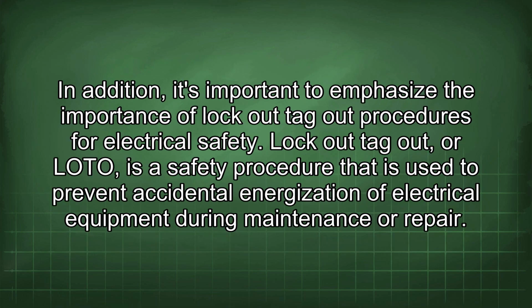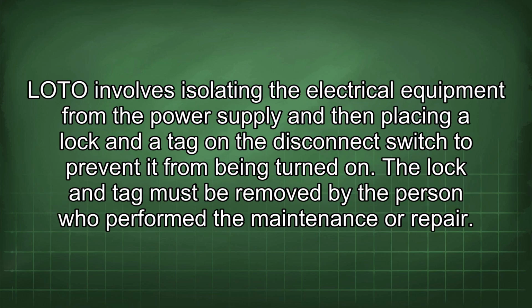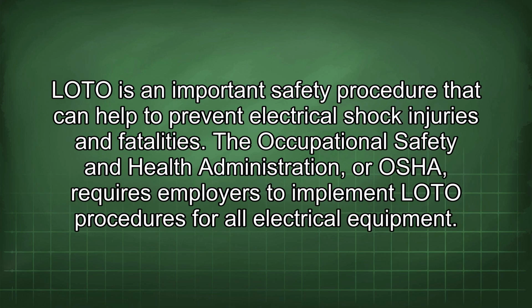hazards. In addition, it's important to emphasize the importance of lockout-tagout procedures for electrical safety. Lockout-tagout, or LOTO, is a safety procedure that is used to prevent accidental energization of electrical equipment during maintenance or repair. LOTO involves isolating the electrical equipment from the power supply and then placing a lock and a tag on the disconnect switch to prevent it from being turned on. The lock and tag must be removed by the person who performed the maintenance or repair. LOTO is an important safety procedure that can help to prevent electrical shock injuries and fatalities.